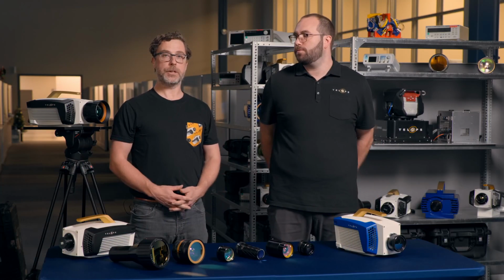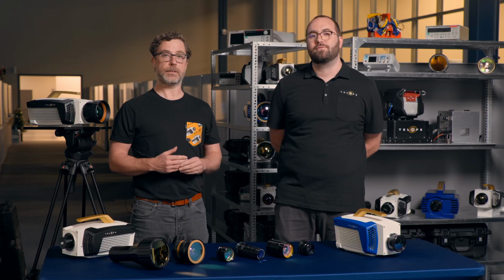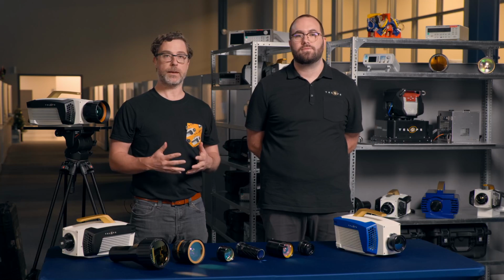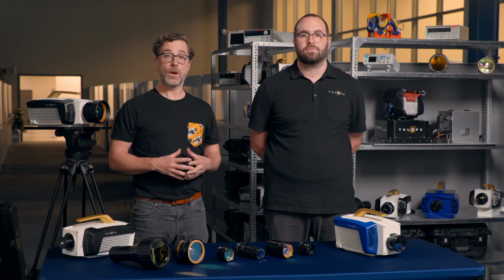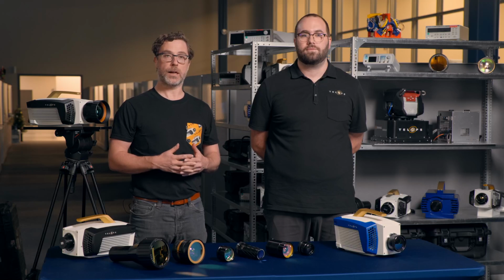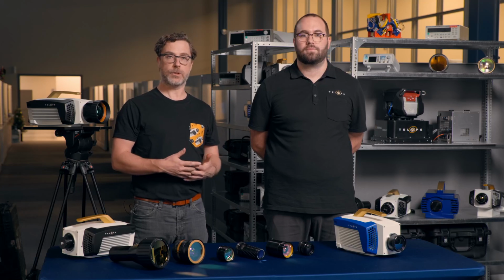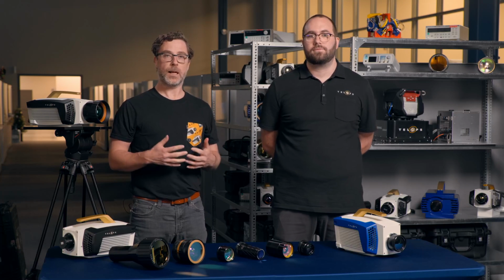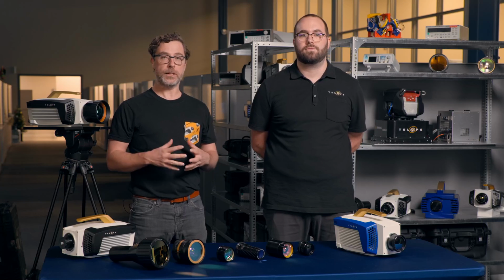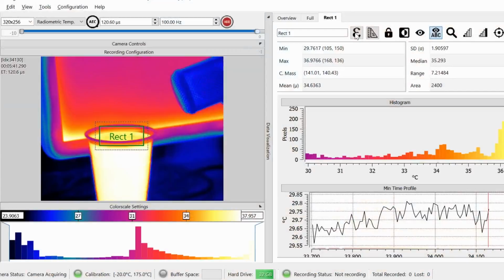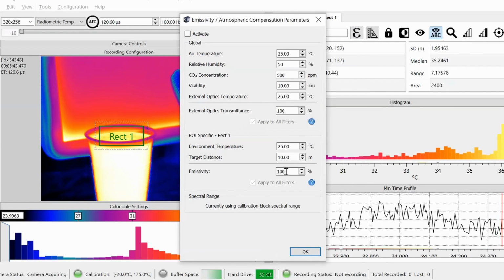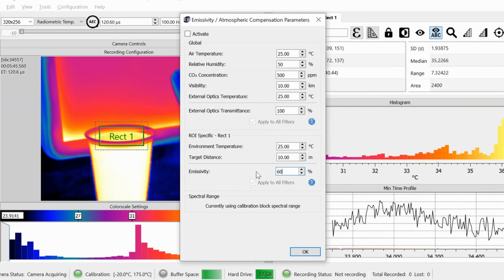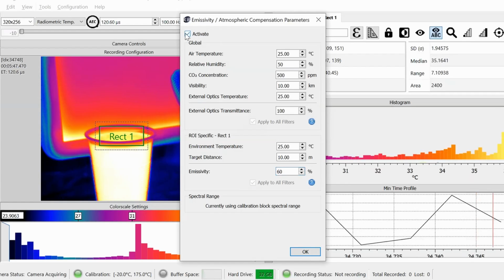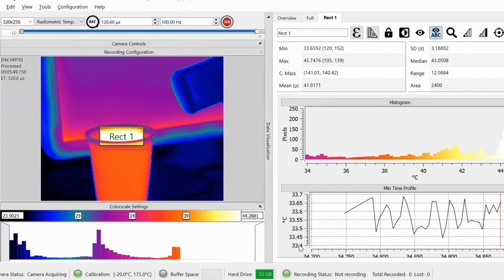For challenging applications, which require a high degree of accuracy and sensitivity despite changing measurement conditions, or under constraints which do not allow for repetitive and time-consuming blackbody calibration, Telops Global Calibration offers a unique and effective solution. By appropriately assessing and adjusting these instrument, environmental, and target parameters within Telops Reveal IR software, Telops systems are able to retain radiometric accuracy up to 2500 C.